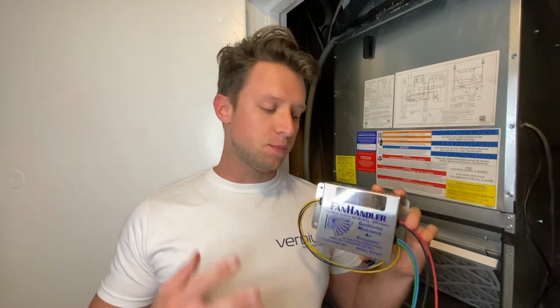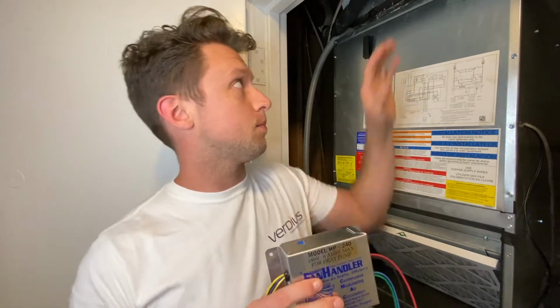The fan handler is a pretty ingenious piece of technology. It's basically a variable frequency drive for the permanent split capacitor motor in your evaporator. It modulates the fan speed based on the sensed temperature in the supply air duct. This capability is helpful in many ways, the first being that you can take advantage of affinity laws that dictate fan power is proportional to the cube of the fan speed.